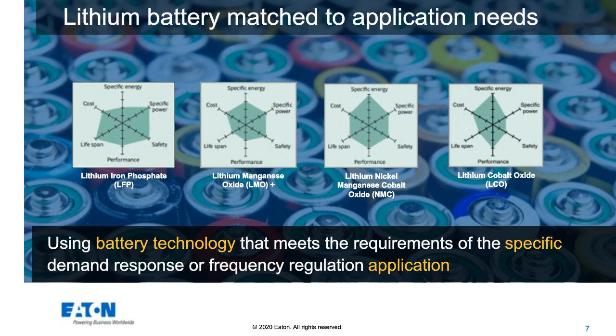For these applications, for grid-tied requirements, we're typically looking for a high specific energy. If you look at the two charts on the far right, you see the specific energy is very high compared with the ones on the left. That translates directly to longer backup times and more ability to run for a long period of time if necessary. Specific power, on the other hand, is the benefit of the two chemistries on the left, and they provide the capability of dumping a lot of energy very quickly into a load, like we often see in data center applications that may have battery backup power requirements of less than 5 minutes. So we have a choice of chemistries and products available, but for energy storage application and dual-purpose UPS, the higher specific energy is usually going to be the first choice.